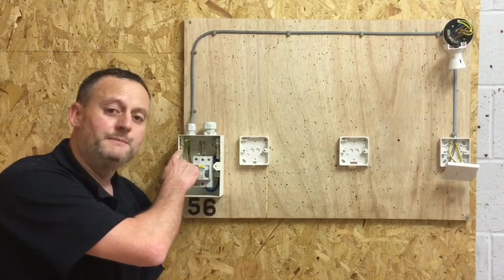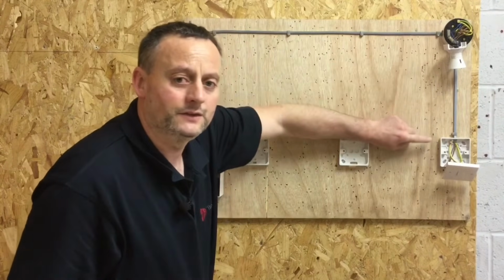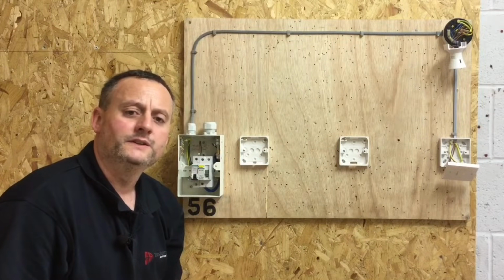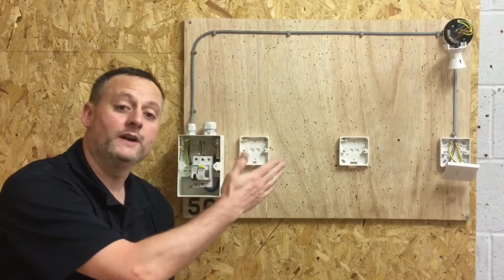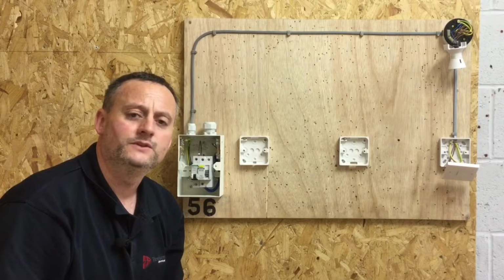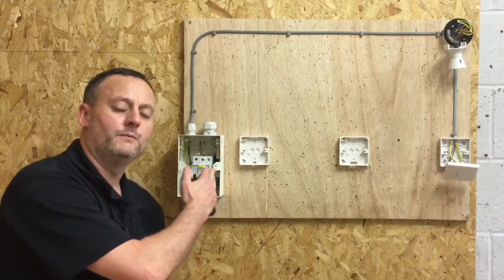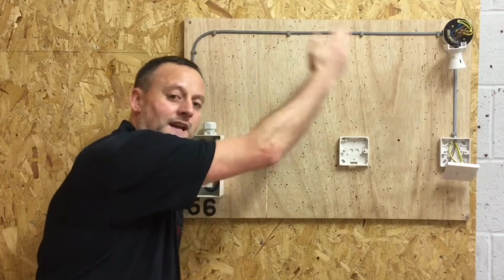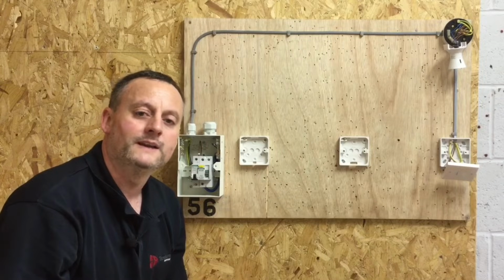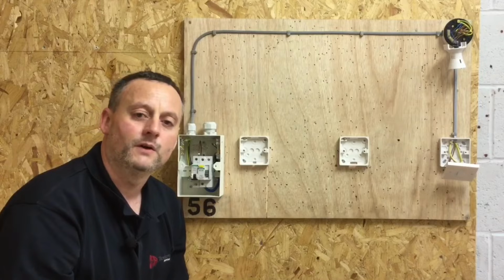I want to prove that the CPC gets from the consumer unit to the lighting point and also down to the switch. We should perform this test at every single lighting point and switch on a circuit. We only have one light and one switch on ours. However, if in industry you had 10 lighting points with 10 switches, the test would be carried out at every light and every switch. And as we progress from the consumer unit to the first room, second room, etc., we expect to see the reading increase as we get to the furthest point of our radial circuit. The further we are away from the consumer unit, the more resistance offered by the cable.